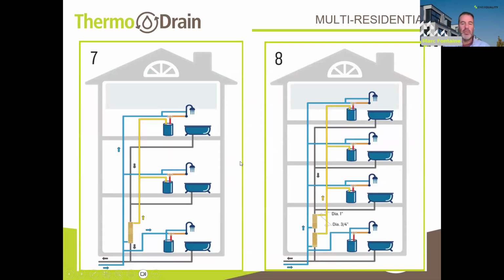So maybe back to the MURB. The 6-plex we were looking at earlier basically has an arrangement that looks like number 7 here. On the right side of the building you have 3 dwellings, and on the left side you have 3 dwellings also. As I mentioned, if you look at it vertically, you have 1 drain water heat recovery unit installed on a drain stack that services the shower or the bathrooms of the dwellings above. And when I say bathrooms, obviously this drain line can also service the kitchen sink and the dishwasher and other fixtures like that. It's not exclusive to the bathroom, but for simplicity, this is how we show the schematics. And so the drain water heat recovery unit would be at the bottom floor, servicing the upper 2 dwellings.